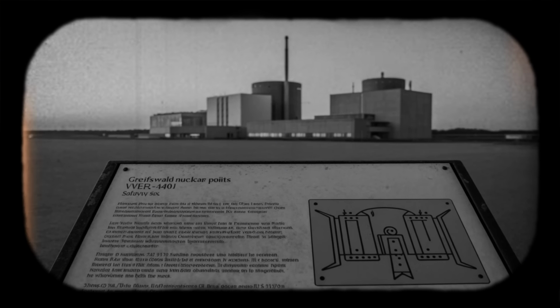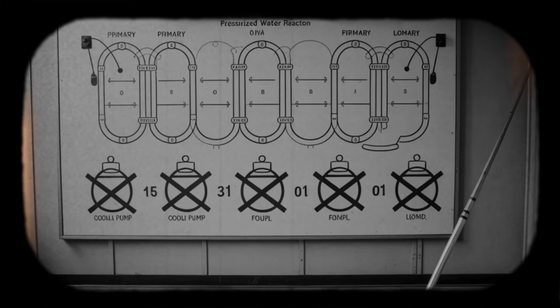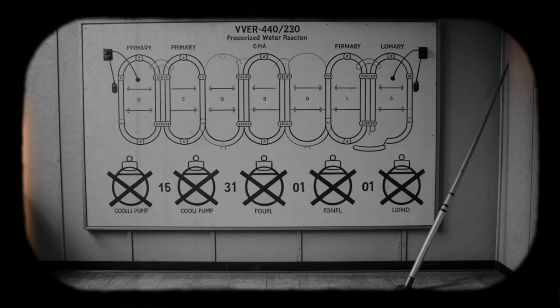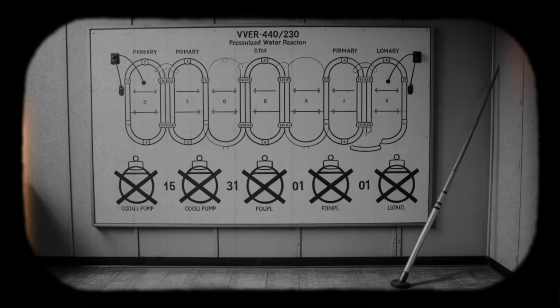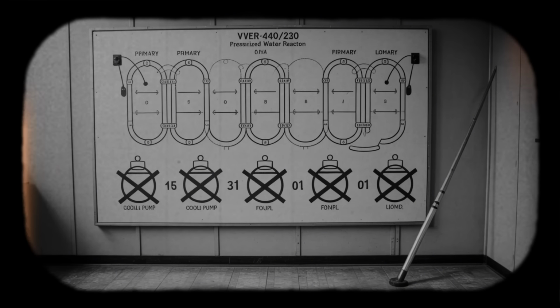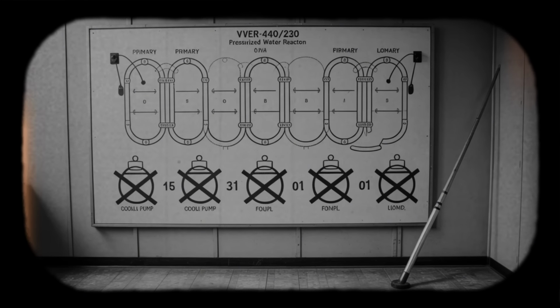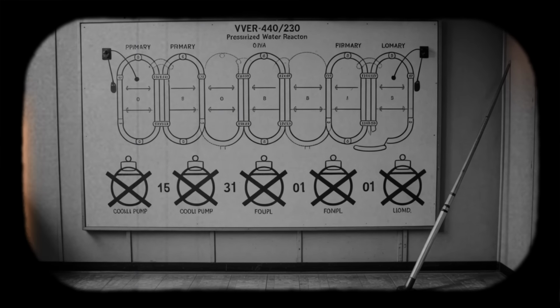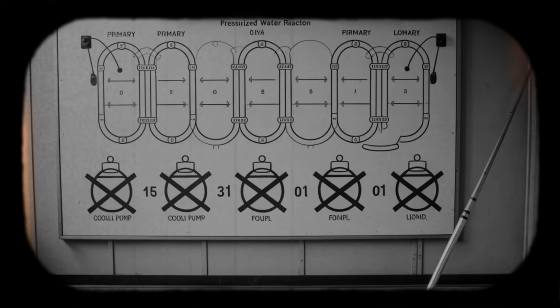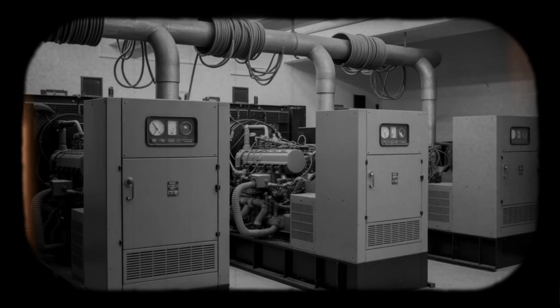Greifswald challenged assumptions. Fire PSA models had often treated cable fires as localized events affecting individual cabinets or small sections of tray. Greifswald showed that a single ignition source could propagate along cable ducts, affecting multiple trains over long distances and extended time periods. It demonstrated that scenarios involving loss of all core cooling for some period were not merely theoretical worst cases, but documented realities. The OECD Nuclear Energy Agency's Fire Risk State-of-the-Art report listed Greifswald among a small number of safety-significant international cable fires. The US NRC's NUREG/CR-6738, analyzing risk insights from fire incidents, included Greifswald in its selected cable fire compilation. IAEA experience summaries cited the event when discussing internal hazards and defense in depth.